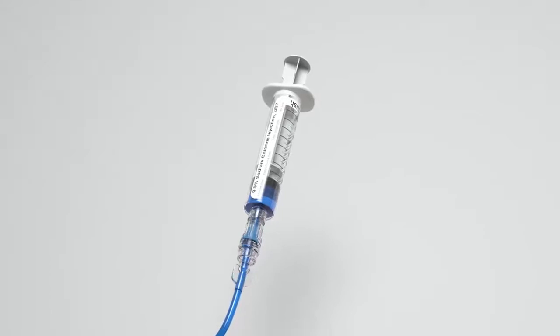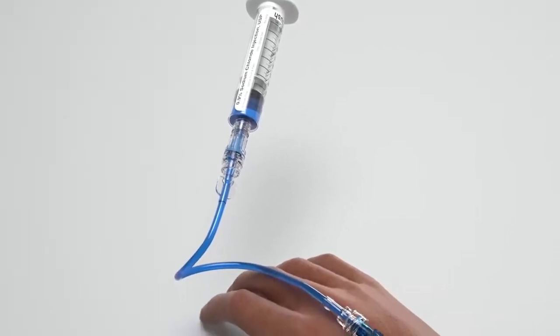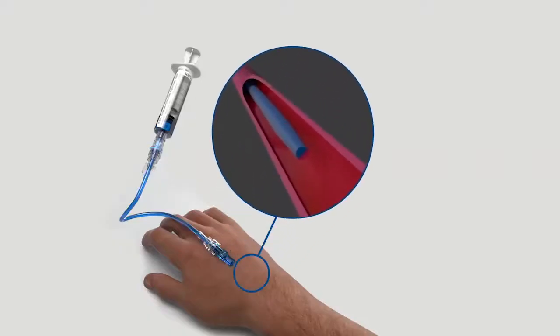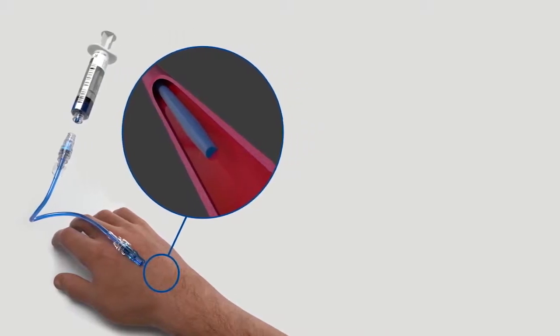The clamping sequence when disconnecting from the connector is determined by a needle-free connector's displacement type. A positive displacement or neutral clamping sequence needle-free connector proactively clears the catheter tip via anti-reflux technology. It does not reflux blood into the catheter regardless of clamping sequence.